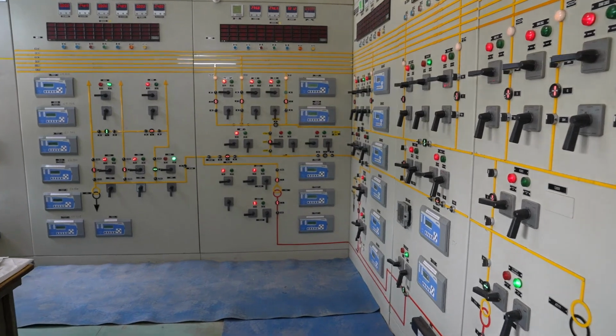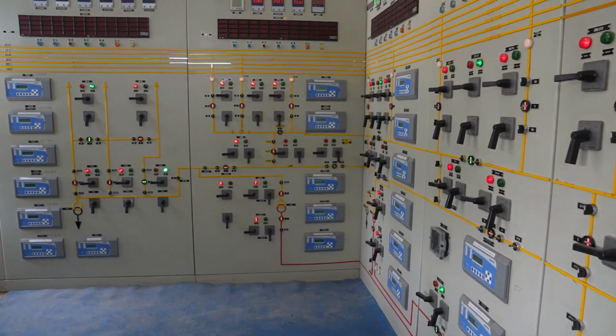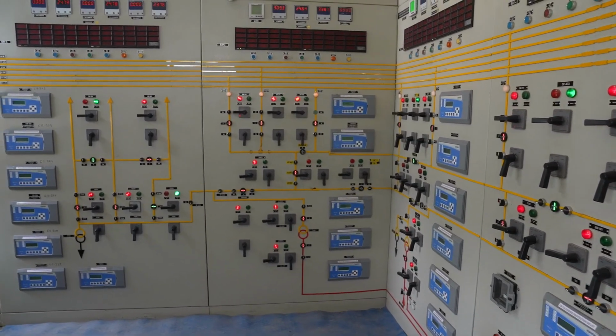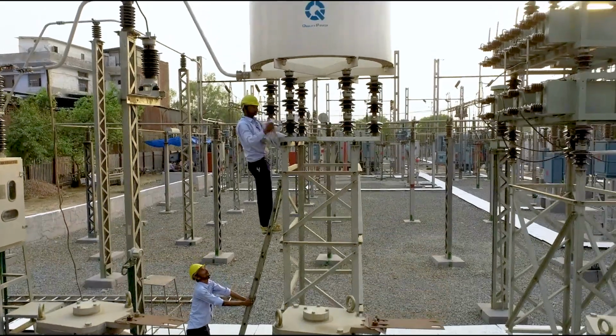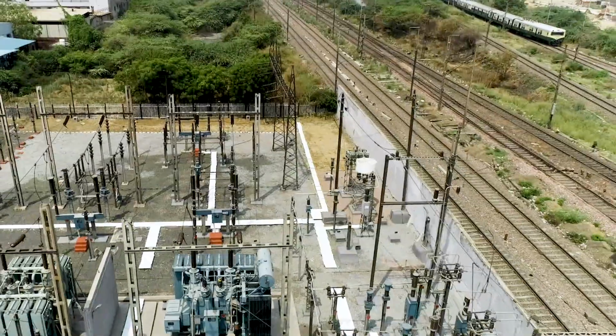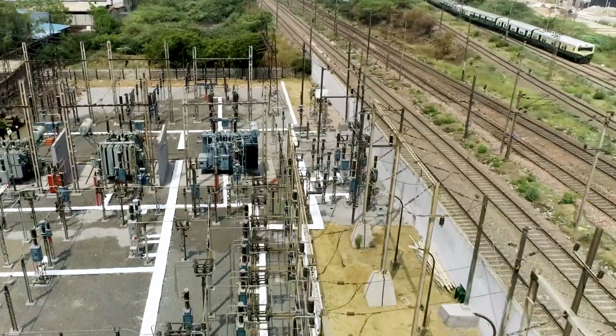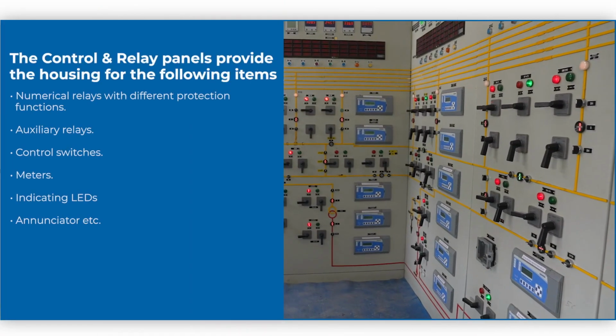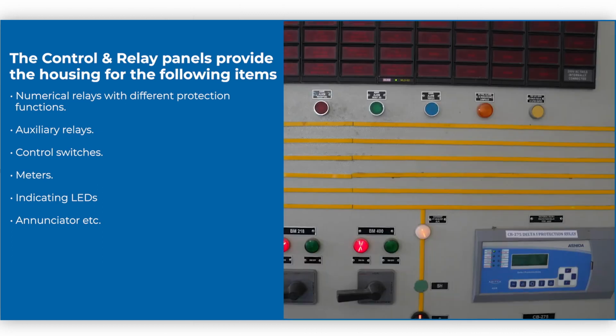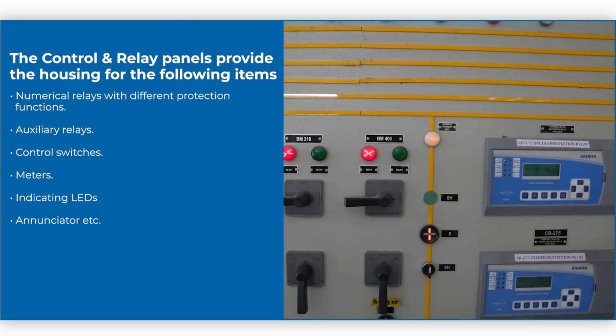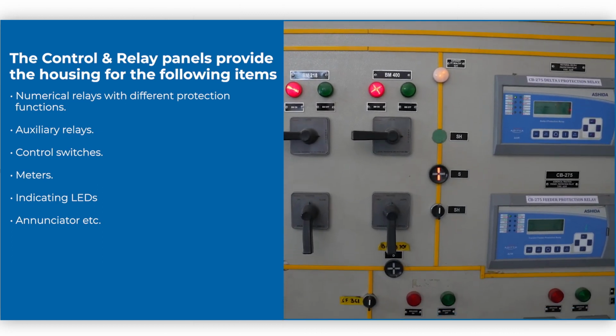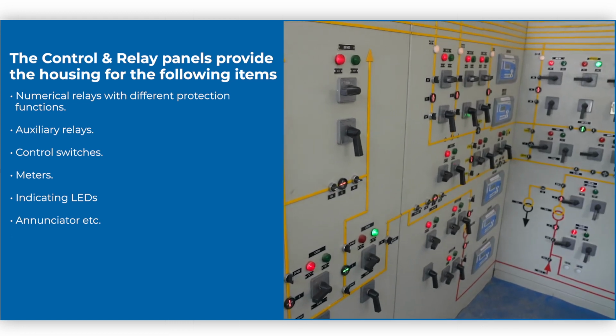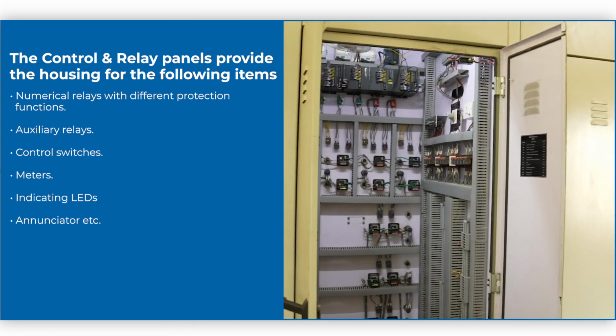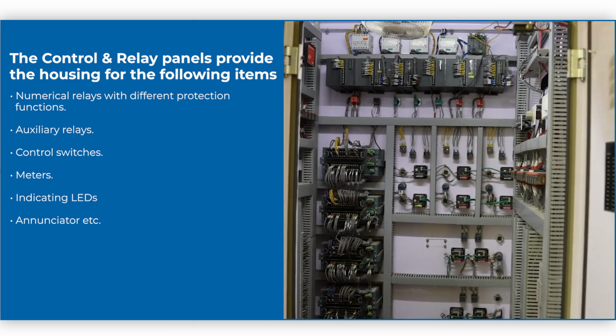This video is related to the maintenance and testing of control and relay panel and remote terminal unit RTU under the series of electrical assets maintenance in 132 kV to 27 kV conventional railway traction substation. The control and relay panels provide the housing for control and protective relays, switches, indicators, meters, etc. necessary for efficient control and protection of substation equipment and feeders.